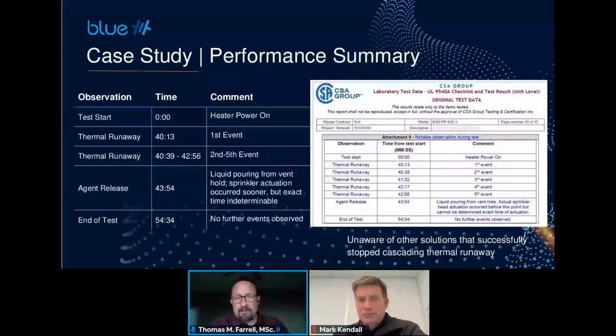And using something like blue, which doesn't work like water: water you would put in, it boils, it goes away. Clean agent you would put in, it boils at a much, much lower temperature, and so it evaporates much, much faster, and also puts out flames, but doesn't really do anything to cool effectively. Blue has a much higher boiling point. It does have multiple stages of action that it goes through to manage that thermal threat, but its very high boiling point also means that it's going to stick around. It's not going to evaporate and just become gaseous and let the battery dry out and start its process all over again.